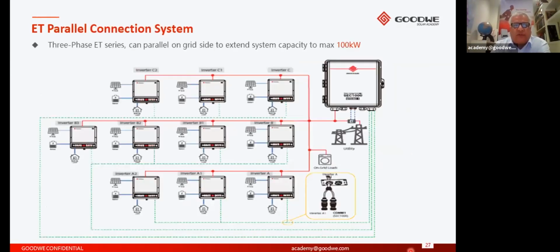One of the extra functions from the ET is, for instance, if you have say 100 kilowatts on the roof or 60 kilowatts on the roof, but in this example for 100 kilowatts, you can have 10 ET units connected in parallel, all with a separate bank of batteries. Each of these banks, depending on the battery manufacturer, whether it's Pylon or BYD for instance, can be from 11 kilowatt hours storage up to 22 kilowatt hour storage per battery bank. So that's quite a lot of storage there.